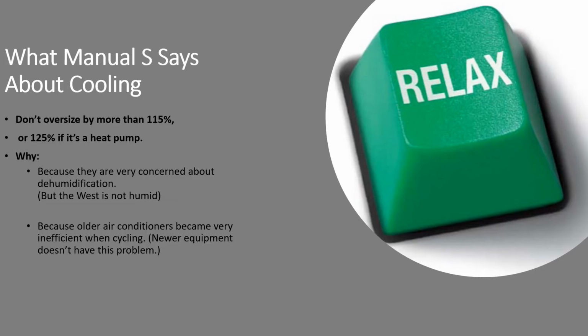What Manual S says about cooling, don't oversize by more than 115%. That's hard, no more than 125% if it's a heat pump. Why are they so worried about this? Because they're worried about dehumidification. The good news is that we don't have to worry about dehumidification in the summertime in the Northwest. If that air conditioner is running at all because it's hot, it will provide sufficient levels of dehumidification.